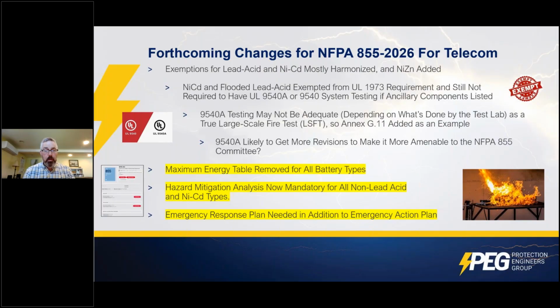And I think there's a maximum energy storage, maximum energy table that would limit what size of an installation could go, particularly in an indoor non-dedicated use building. Lead acid and NiCad did not have a maximum energy limit, which lithium, flow batteries, and other chemistries did. If you wanted to exceed the maximum allowable energy, you could do it, but you basically needed to do a large-scale fire test or have 9540A testing that was very positive, acceptable by the AHJ, and have a hazard mitigation analysis showing that it was okay.